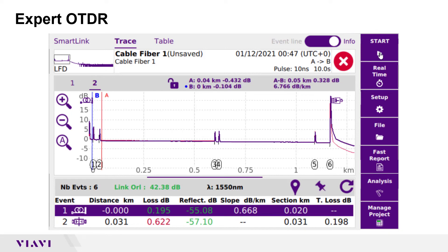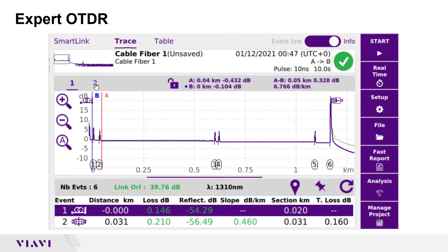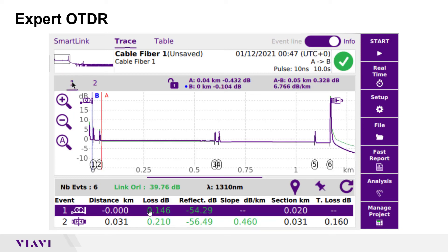When all acquisitions are complete, the top section of the screen can be set to choose a display format and the event line type. When trace is selected, I recommend the info view so that you can view the minimap and the pulse width used for this acquisition. Graphical results for each acquisition are shown in different colors in the center display. Tap the numbers to select the wavelength and pulse width for display. Distance, loss, and reflectance for the first event is shown in the lower display.